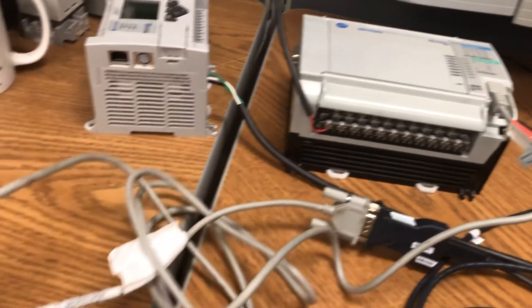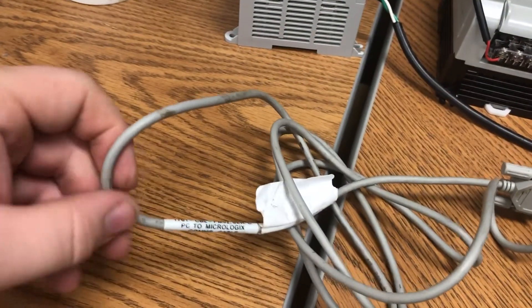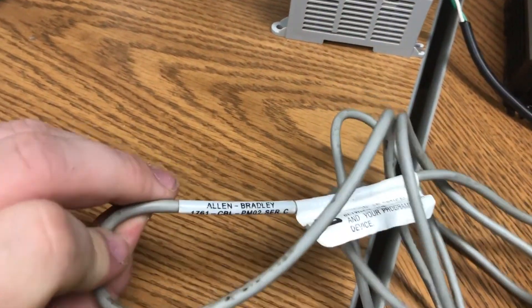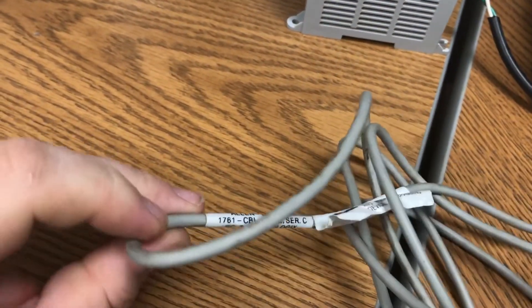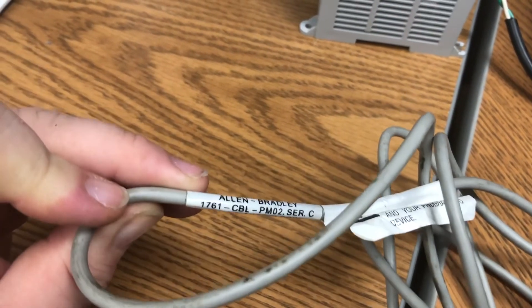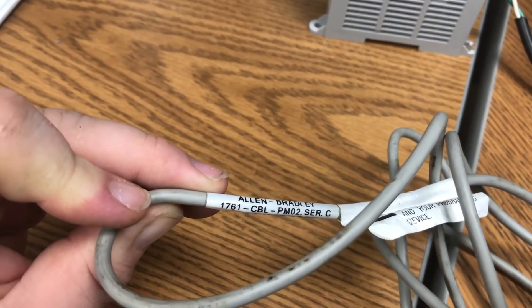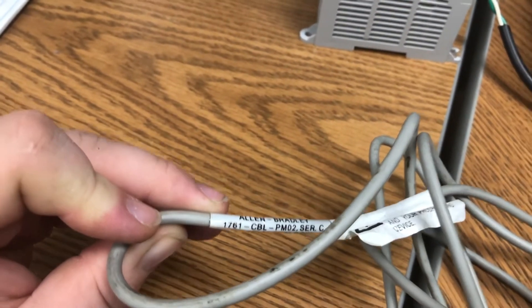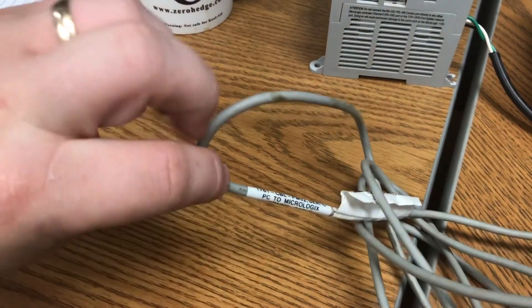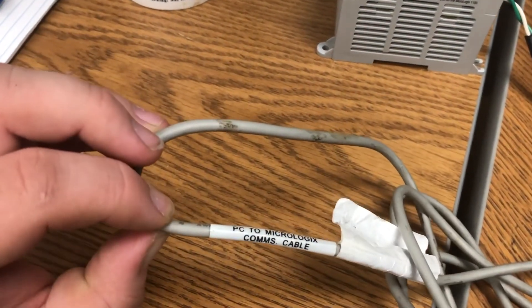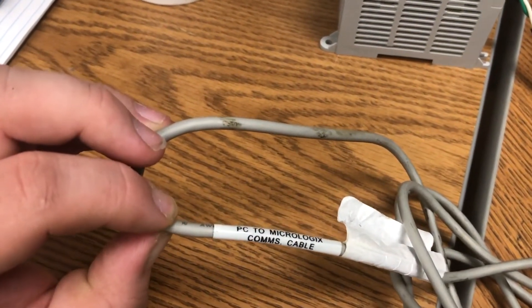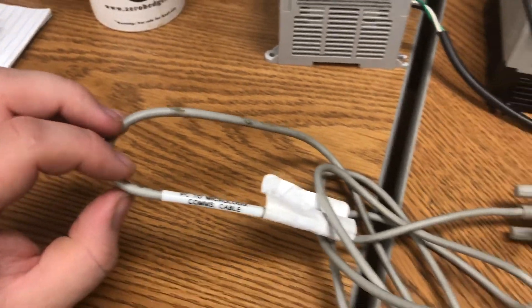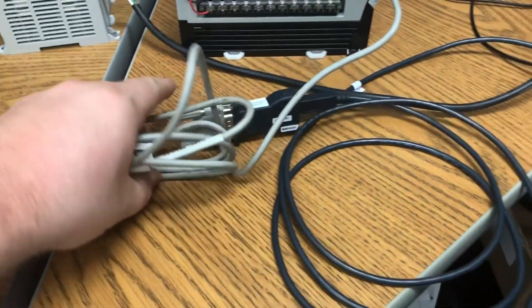So you're going to need this cable for a Micro. Allen Bradley 1761-CBL-PM02. This one happens to be Series C. It says right on it PC to Micro Logix COM cable. You do need this cable.